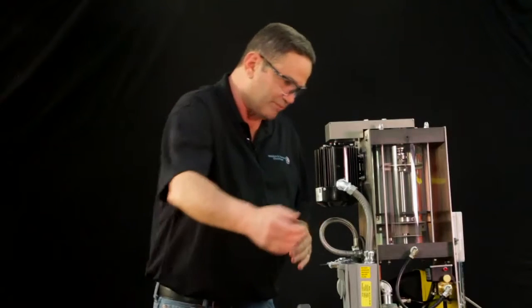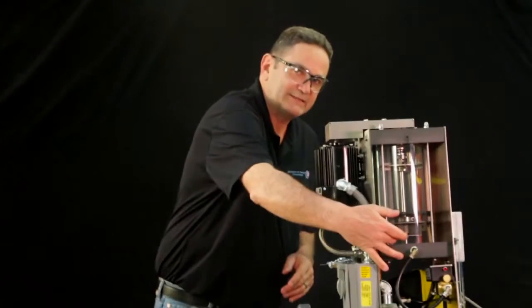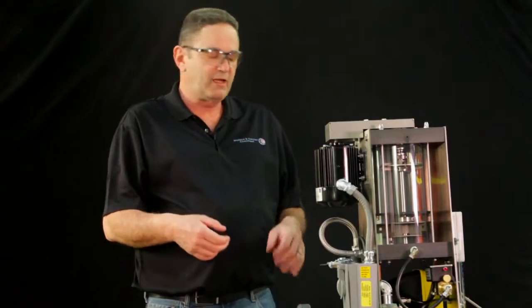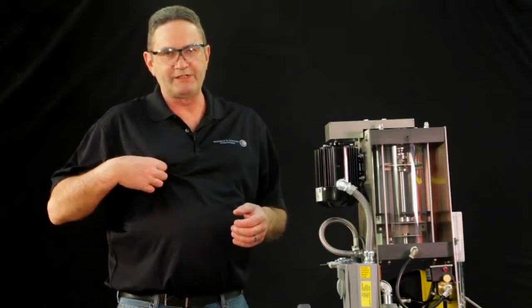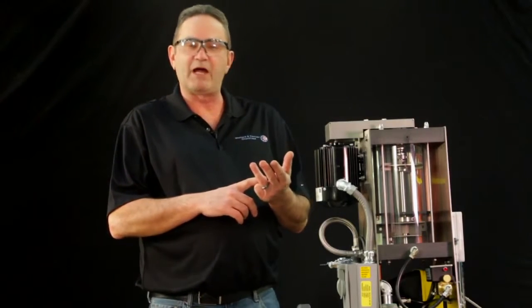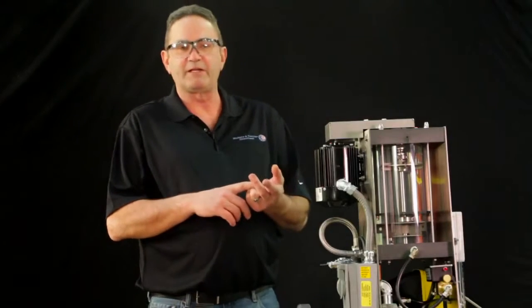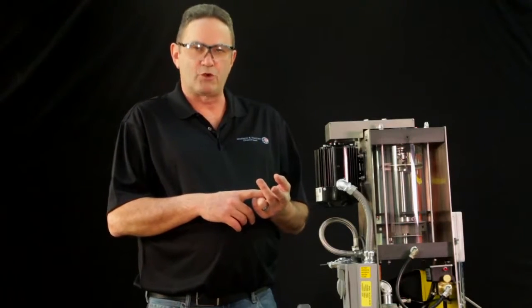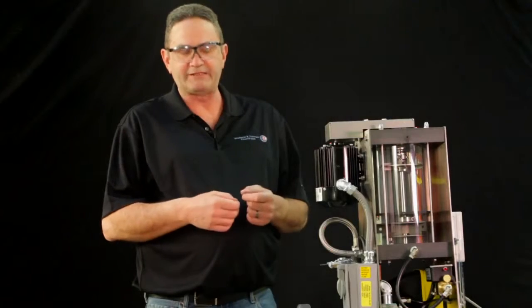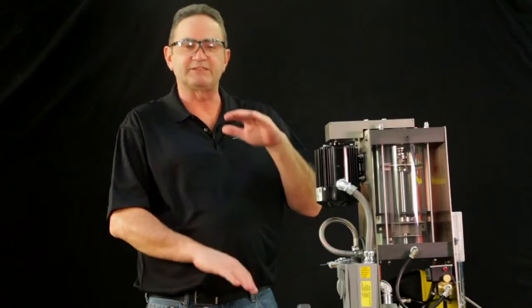The next would be your polymer injection check point, located inside your mix chamber. You notice that you have water migrating back into your polymer line, and you basically start pulling a stringer. A stringer is where you have non-activated polymer with no energy, and it prevents the check valve from closing. Majority of the reasons for that is improper mixing of the neat polymer tote. If you're coming out of a 5-gallon bucket, before you use it, make sure you shake it up. If you're using a 55-gallon drum, I always recommend that you get a drum mixer.